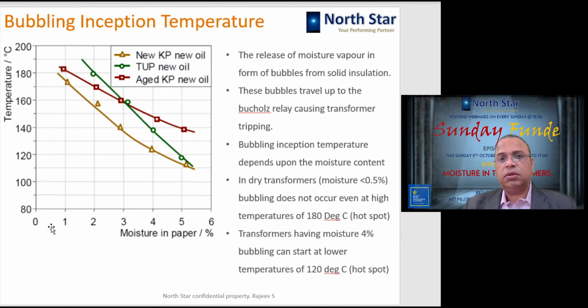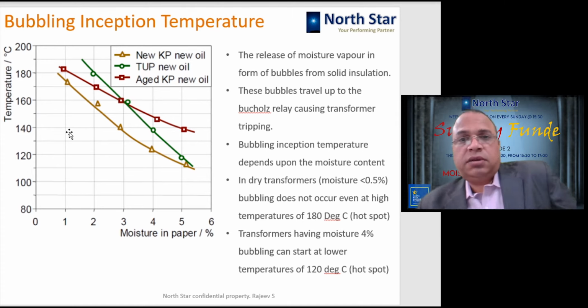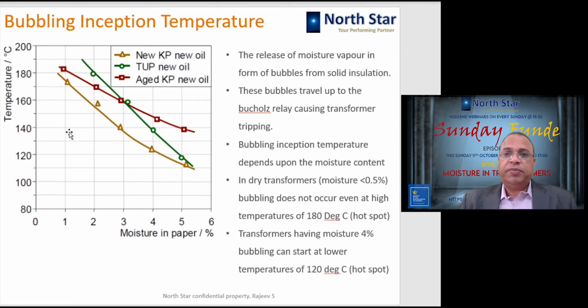Okay, so when the moisture is low, the bubbling will happen in this case somewhere around 172 degrees centigrade, and if it is further dry, around 180 degrees centigrade, nothing will happen to the transformer, no bubbles will come. So what is happening is that when the transformer has a lot of moisture, the moisture trapped in the solid insulation is converting into vapor, and that vapor is getting released from the insulation.